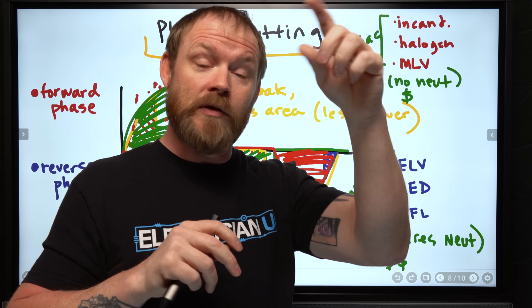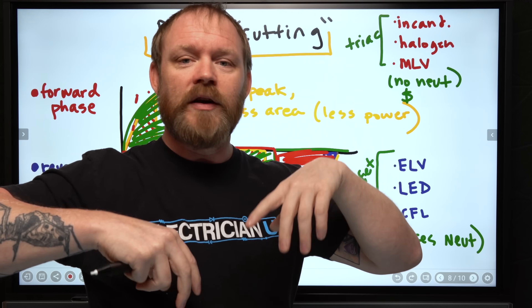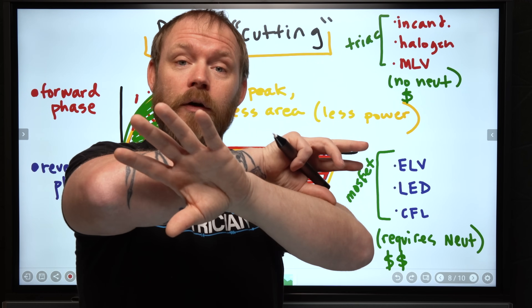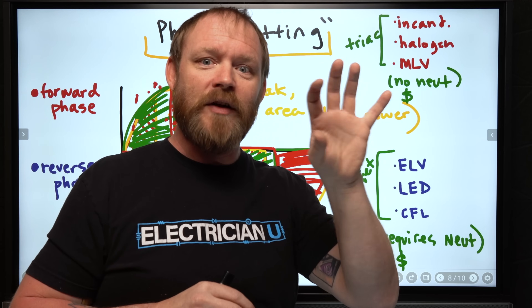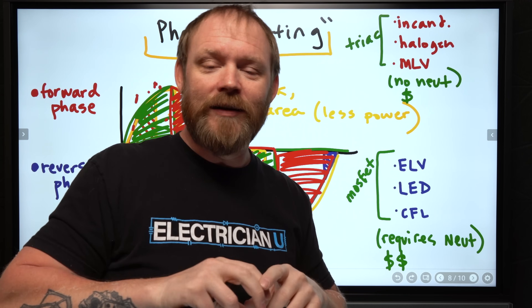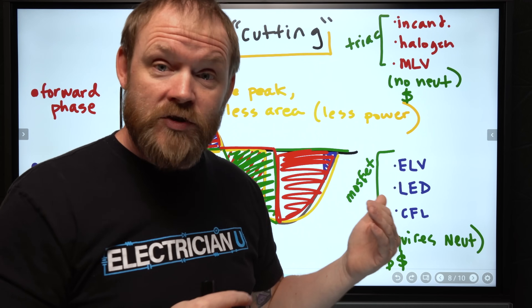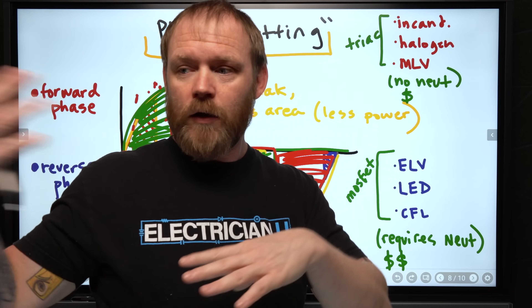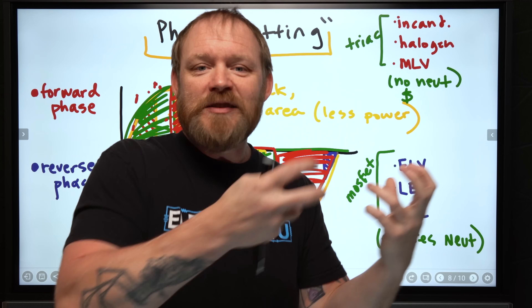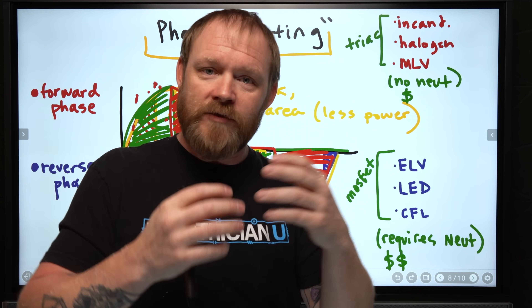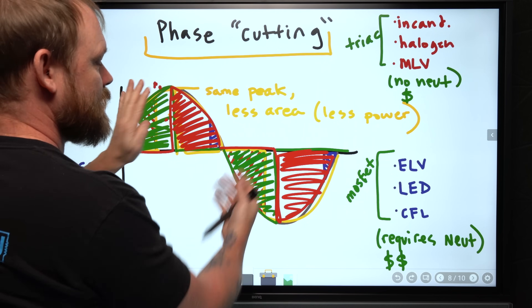If you've done lighting control systems - Crestron, Lutron's Homeworks, RadioRA 2 or 3 - some of them let you actually program in forward phase or reverse phase. So if you have weird fluttering issues in some light bulbs, research the bulb and figure out whether it was designed for reverse phase or forward phase. A lot of times switching from one to the other can fix the problems. If you have a really advanced bulb and a really advanced dimmer giving you control over this, but they aren't perfectly matched, you'll have issues.